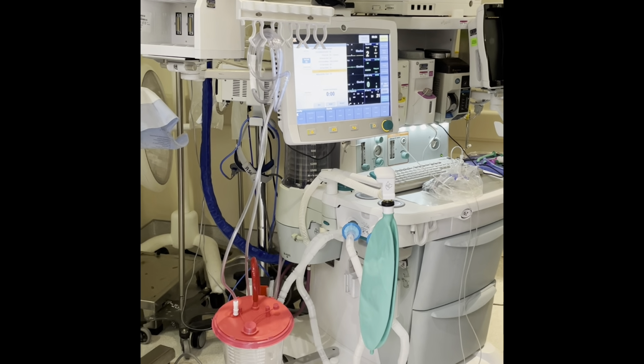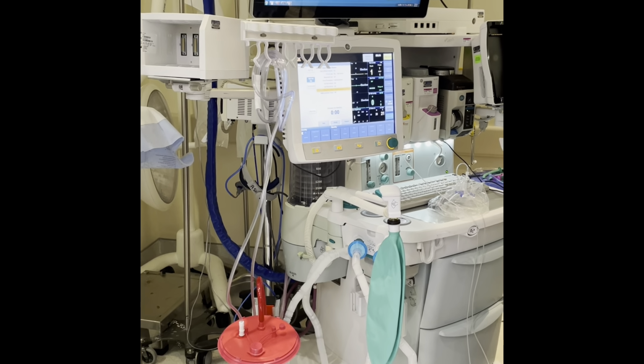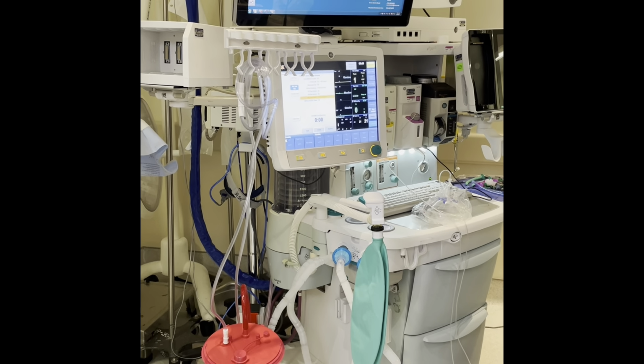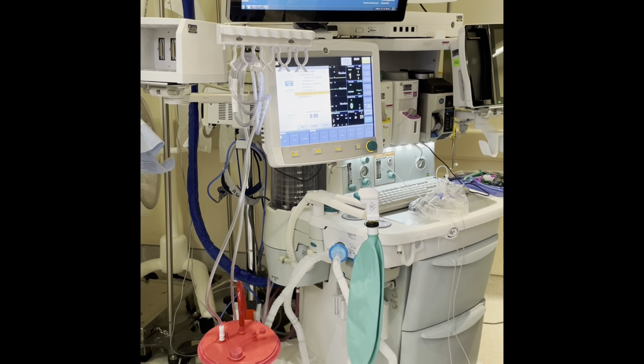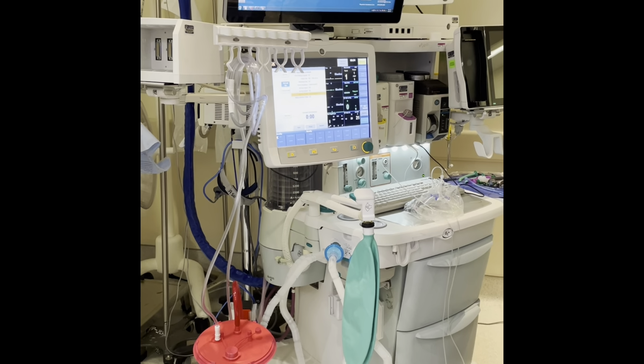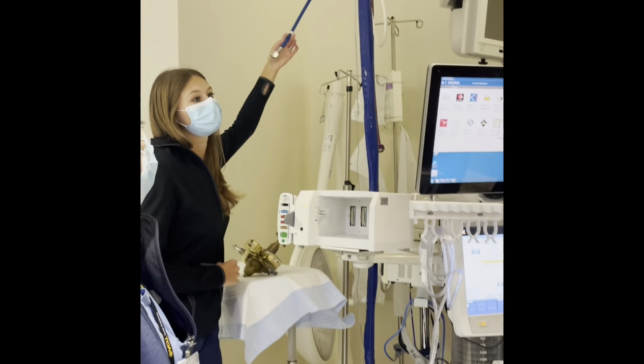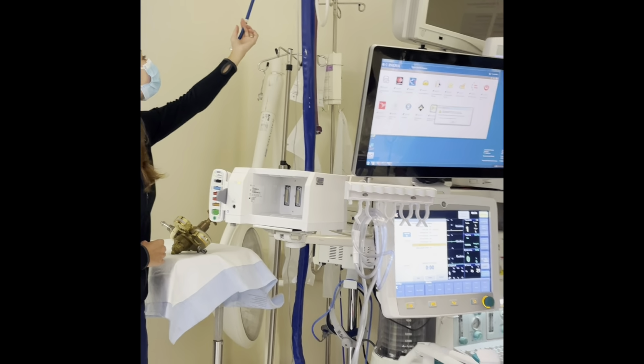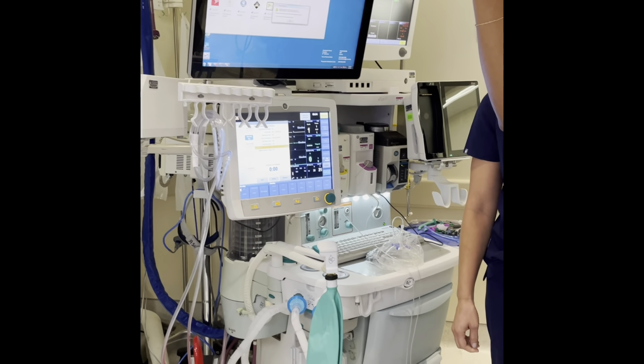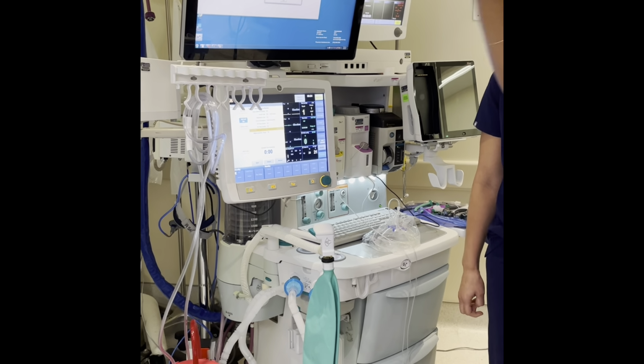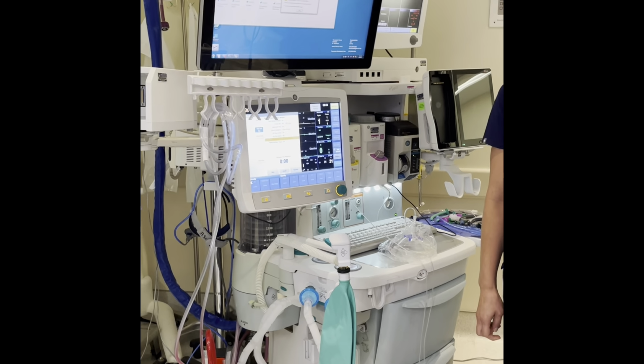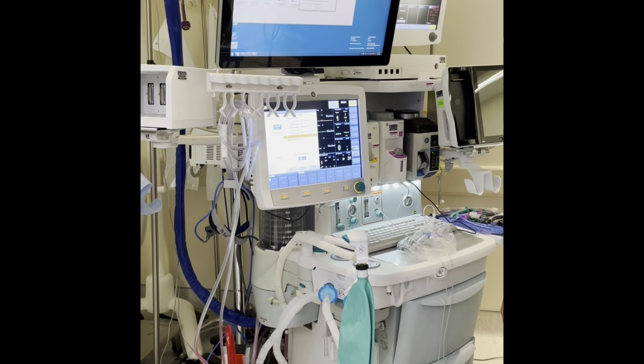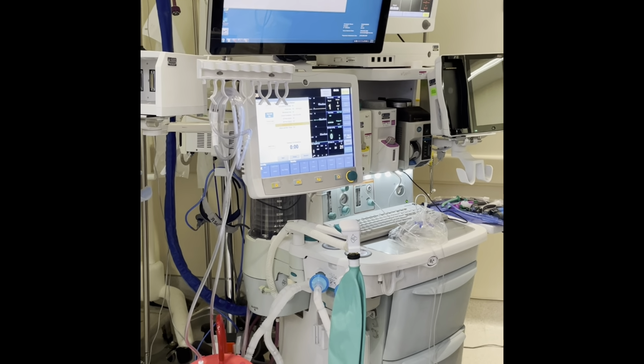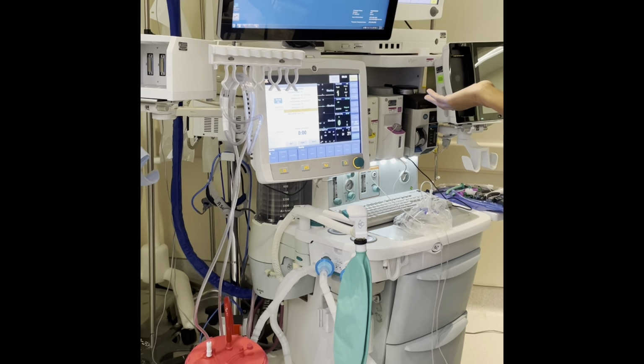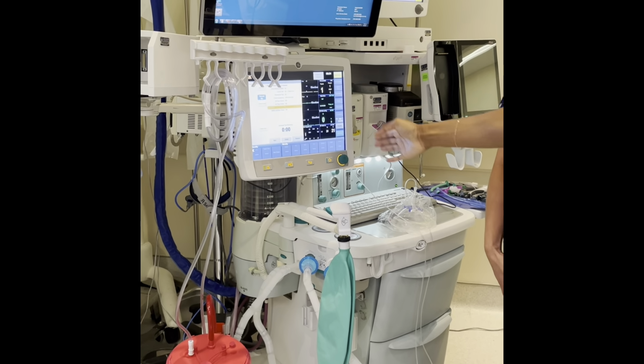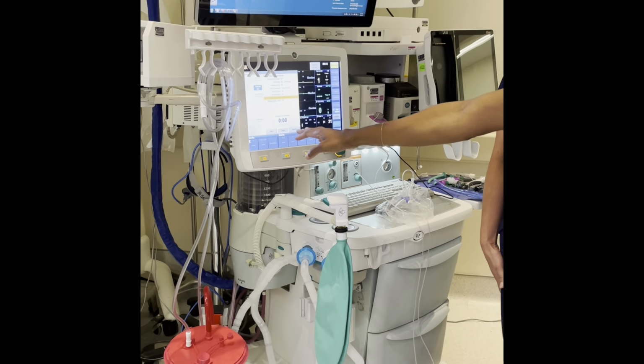Okay, so it's telling us there's no nitrous pressure because there's no nitrous pipeline pressure. When it's doing the check, it's doing it from the pipeline. It's not doing it from the O2 cylinders in the back. So they're all color coded. That's why it's telling us that. So if you're doing a check and it says that, and you know you don't have nitrous, just hit accept.